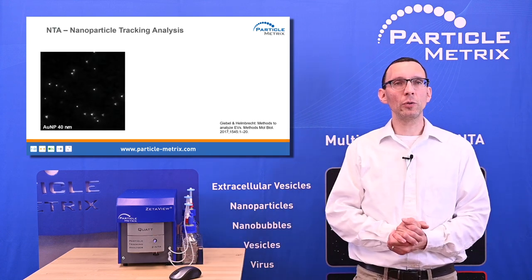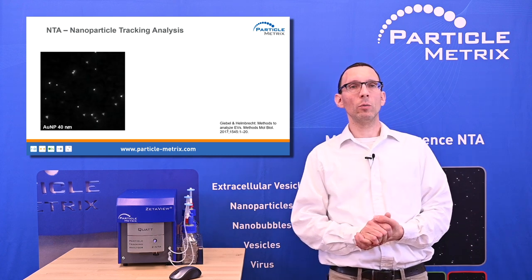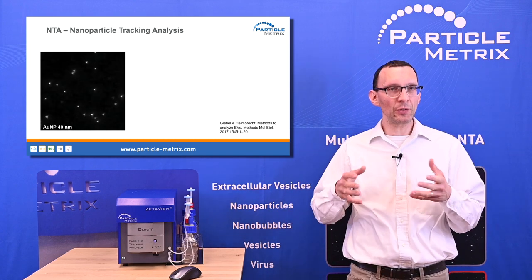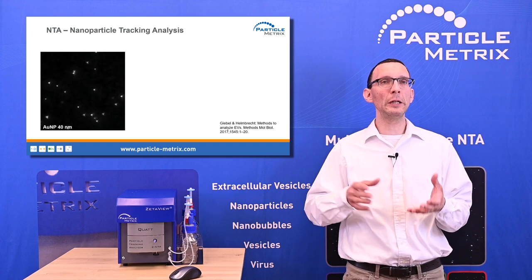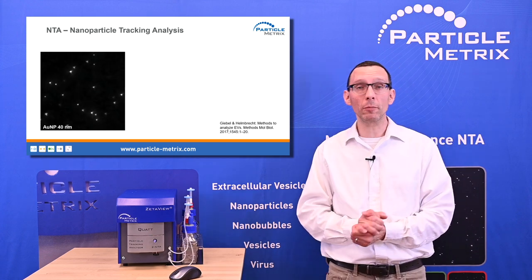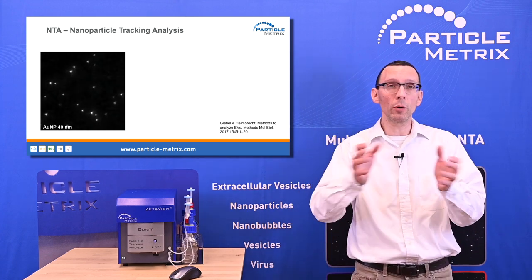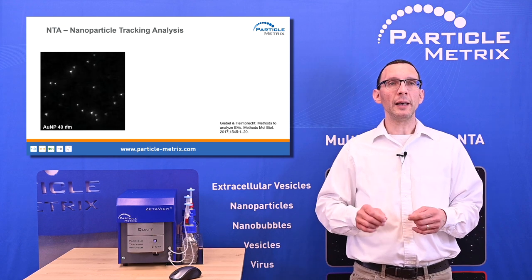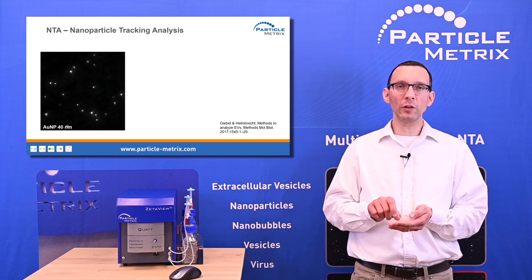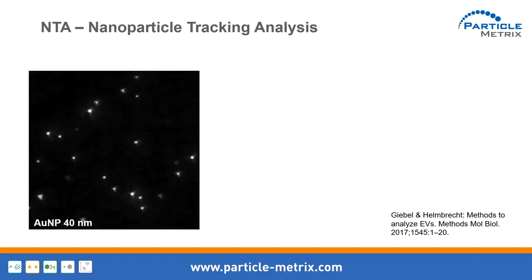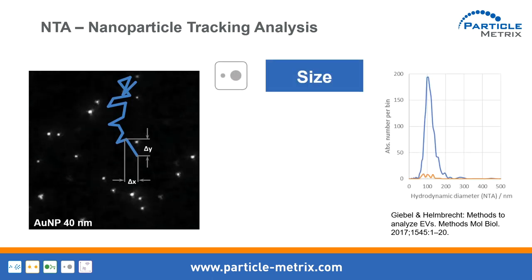Let me introduce those who are not so familiar with nanoparticle tracking what it does. You see the Brownian motion of 40 nanometer gold particles, done by the ZetaView — an ultra microscope. You illuminate with a laser and you see the scattered light at 90 degrees of those particles. The smaller the particles are, the more active they are, and the larger the particles, the slower they move. The algorithm detects the positions and links them, and based on these diffusion properties we derive a particle size for each individual particle. This makes nanoparticle tracking analysis a single-particle analysis tool.